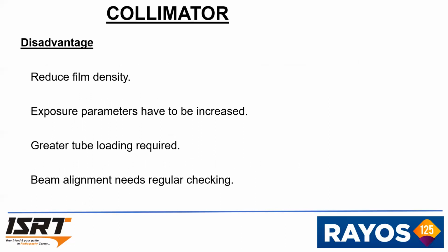Like the previous two, this also has some disadvantages. It reduces the film density. Exposure parameters have to be increased, and greater tube loading is required.